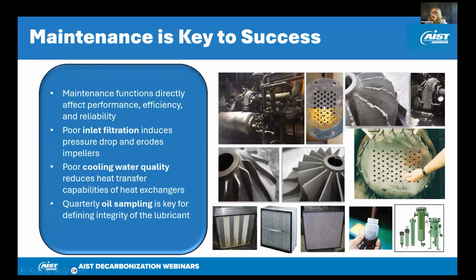And here's an example, poor filtration. We have a brand new impeller here, and you see the corners are squared off of the inducer area of the impeller, which is downstream of the inlet filter. After time of poor filtration, you're essentially sandblasting the impeller, and the edges become rounded out. And when this happens, the compressor loses efficiency.